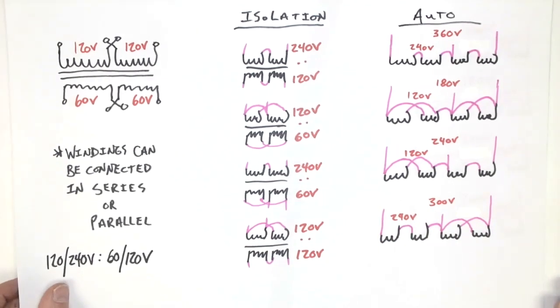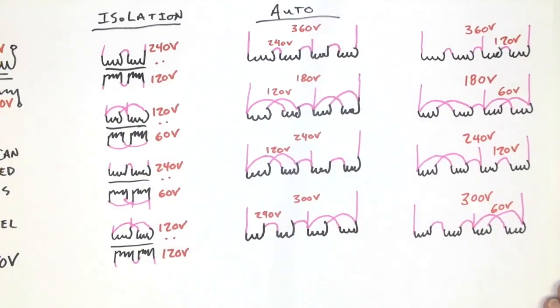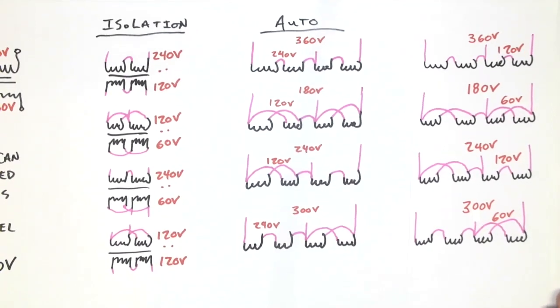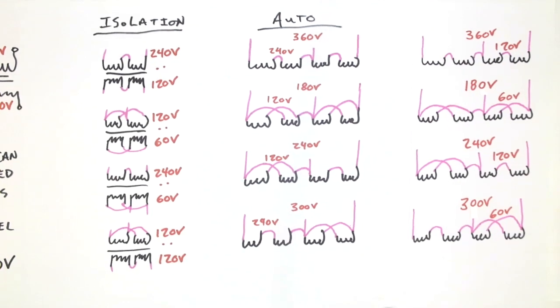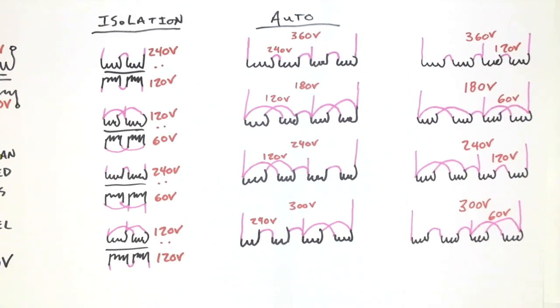Now, there are more connections. Well, not really different connections so much as different termination points for the load. But look at how many different connections we could possibly have for this one transformer. And so you get to see the ramifications of the manufacturer providing a multi-winding transformer because it can service so many different sources of supply and also so many different load voltages.